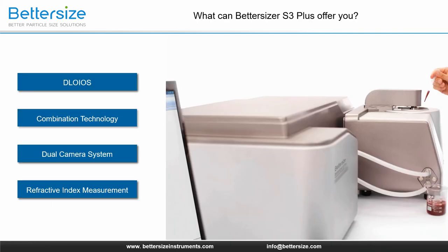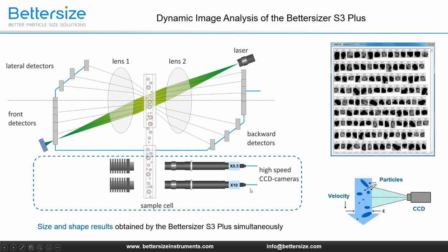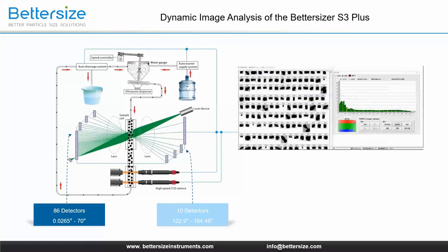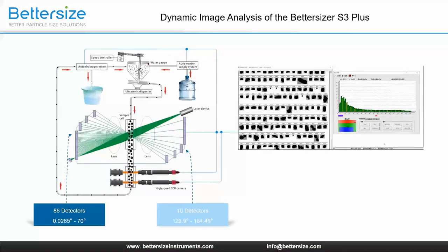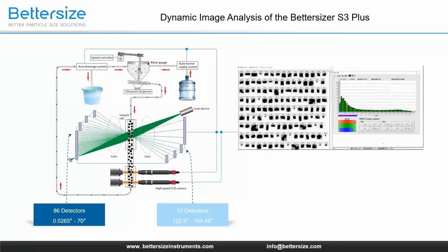Next, I am going to introduce the combination technology that the Bettersizer S3 Plus is very proud of. Let's have a closer look at the optical bench structure. In addition to the classical components for performing the light scattering experiment — lasers, lenses, detectors — a camera system is implemented. These are two high-speed CCD cameras up to 70 frames per second, which enable sharp detection of moving particles at different magnifications, and therefore an additional evaluation with dynamic image analysis. The 0.5-fold and 10-fold cameras record images of coarse particles and statistically evaluate the results. This figure shows the measurement setup.